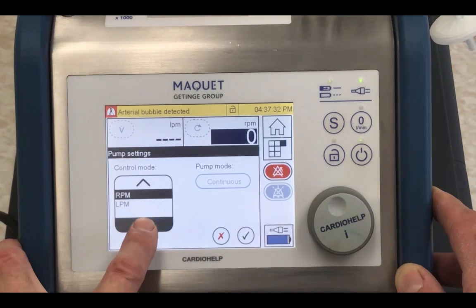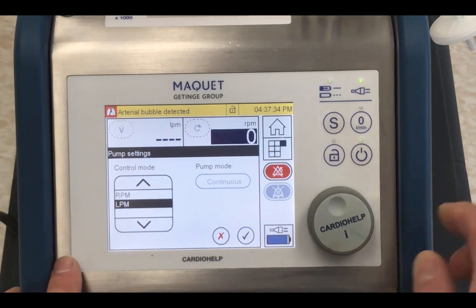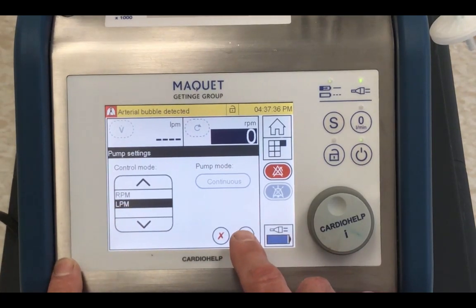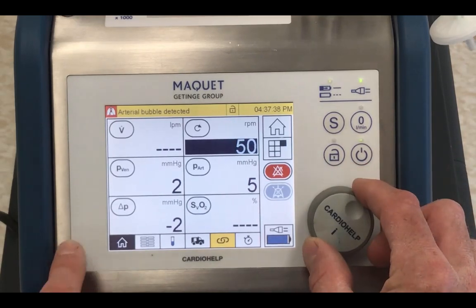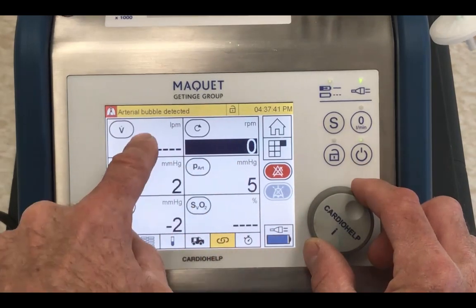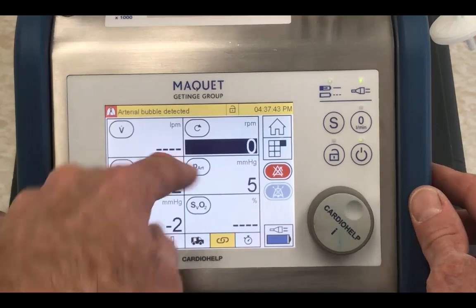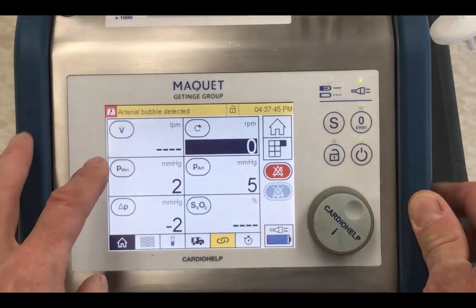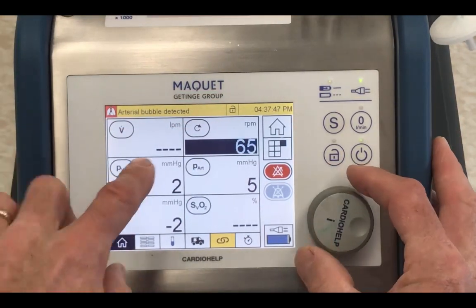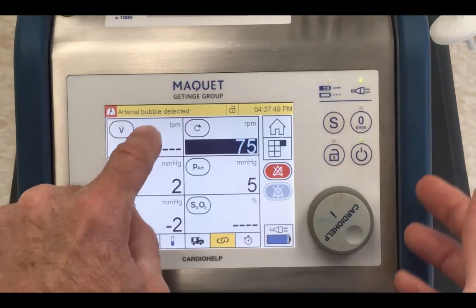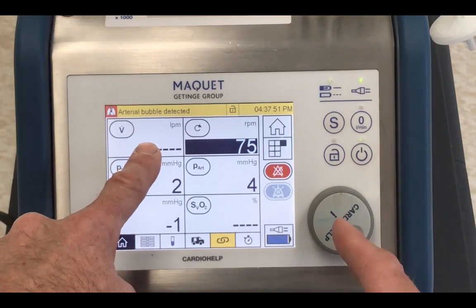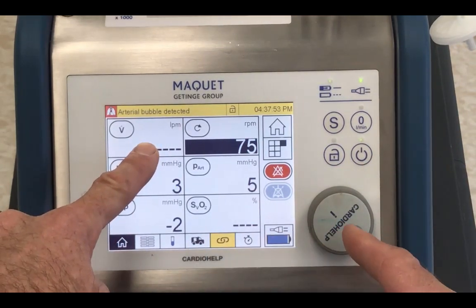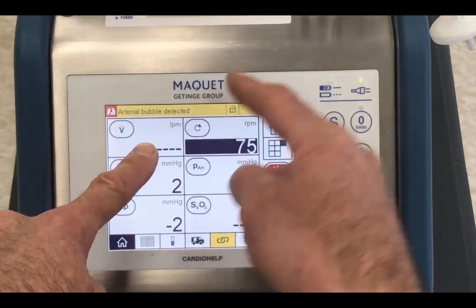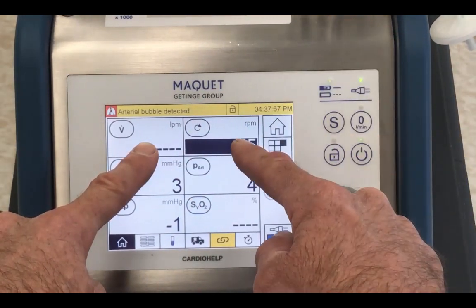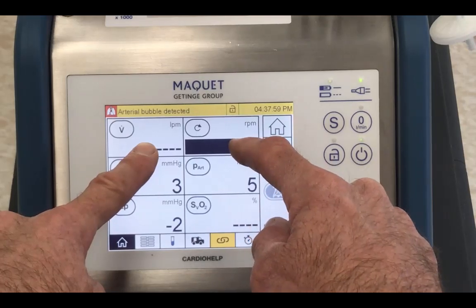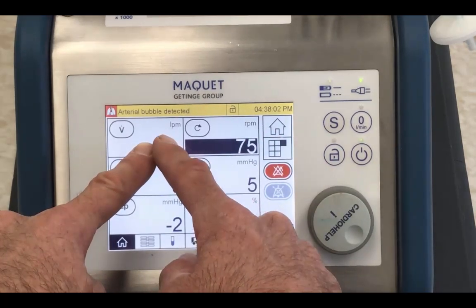If you switch this to LPM mode, then what you've done functionally is as you turn this knob, you are changing the RPMs, but you're setting a flow. I don't have any fluid in the system to show you this. You would turn this and set it, say I take my hands off of this and it says 1 liter a minute. Now, you're in LPM mode. That means that you set 1 liter a minute. The pump has the permission to increase and decrease the RPMs as necessary to maintain 1 liter per minute.